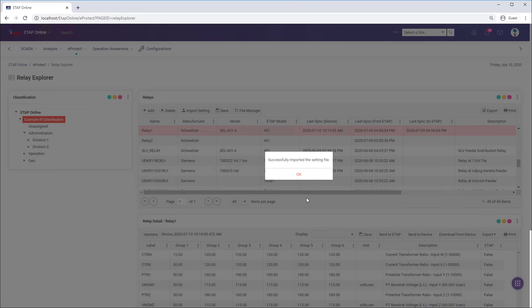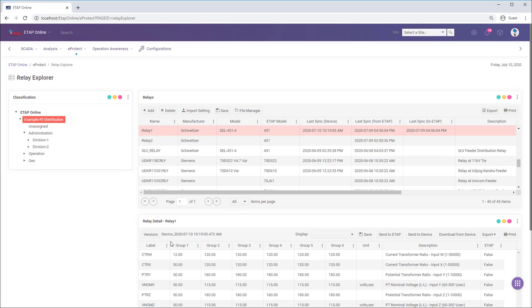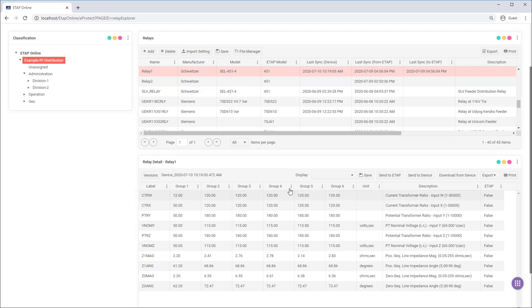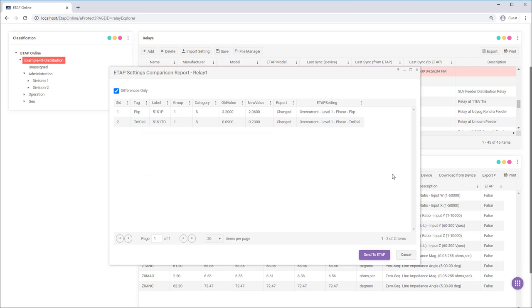Once uploaded, you'll see that the latest sync time has been updated. All the settings are now displayed, and you can see the details of all the parameters for this specific relay. Next, we are going to send these settings to the ETAP digital twin. The comparison report shows the difference between the settings in the current ETAP model and what we are sending through eProtect. We are changing the pickup from 3.2 to 2.06 and the time dial from 0.09 to 0.23.